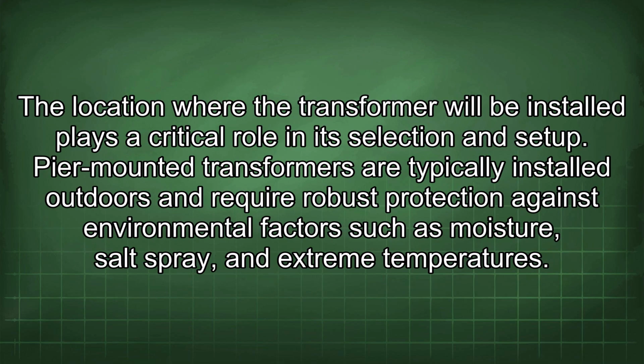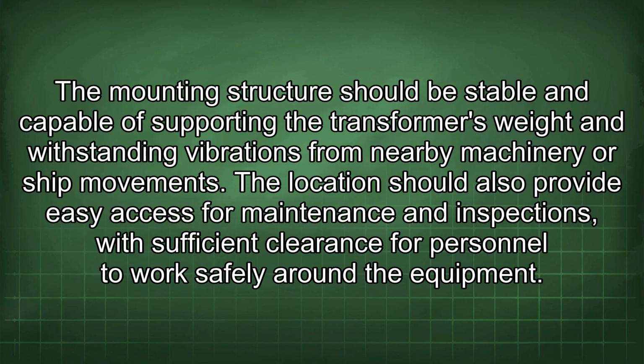The location where the transformer will be installed plays a critical role in its selection and setup. Pier-mounted transformers are typically installed outdoors and require robust protection against environmental factors such as moisture, salt spray, and extreme temperatures. The mounting structure should be stable and capable of supporting the transformer's weight and withstanding vibrations from nearby machinery or ship movement. The location should also provide easy access for maintenance and inspections, with sufficient clearance for personnel to work safely around the equipment.